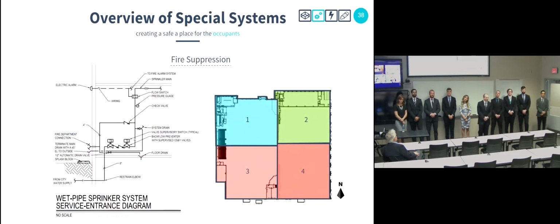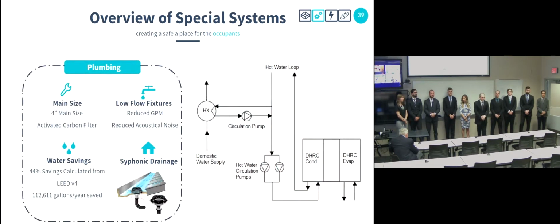The facility is classified as an A4 assembly light hazard facility. The building was divided into 4 fire suppression zones, shown here on the right. On the left is a detail showing the fire suppression entry into the building. By being able to move the domestic water entry to the west side of the building, we're able to minimize the amount of piping needed to deliver domestic hot and cold water to the plumbing fixtures due to the adjacency to the 2 major consumers, the 2 large restrooms. We're also able to reduce overall water consumption by 44% based on the LEED version 4 calculator.